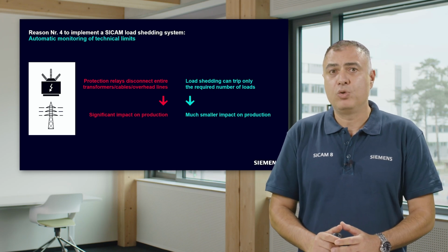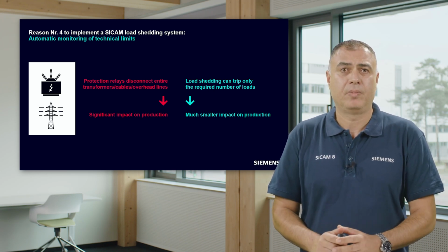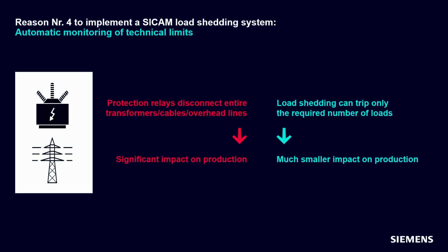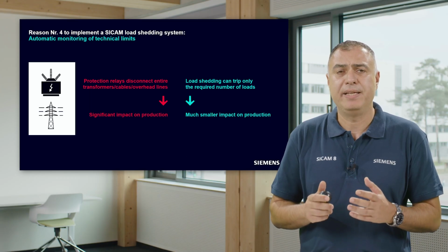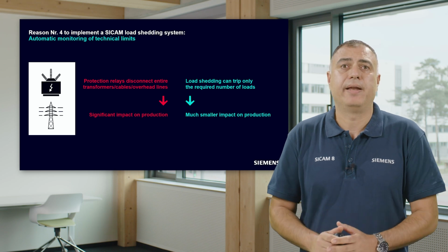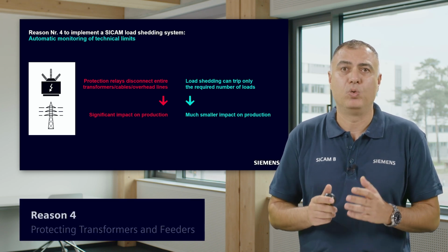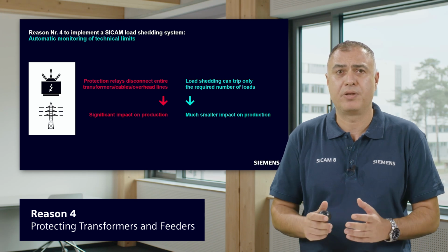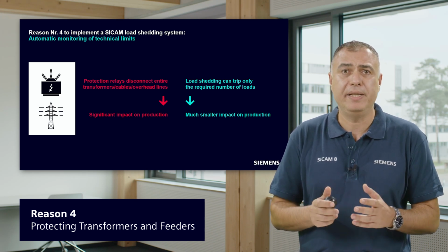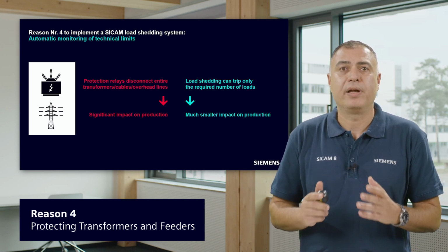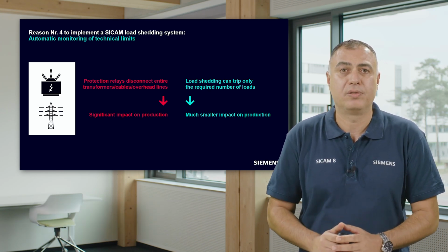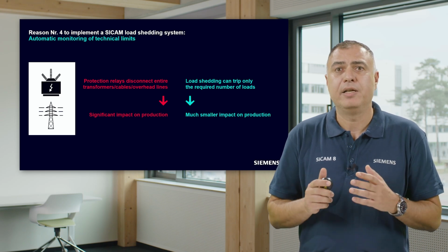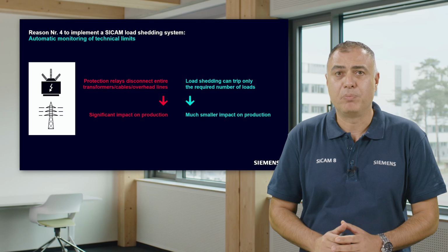Reason number 4. Also, this is a more advanced use case. Usually, the technical limits of transformers and infeeders are only monitored by protection relays. If the transformers or tie lines are overloaded, then they will be completely tripped by these relays. Load shedding installations can offer a much smarter approach. Just before a protection device switches off an entire transformer or a feeder, the load shedding system can shed the required number of connected low priority loads. This can significantly reduce the negative impact on the plant's production.